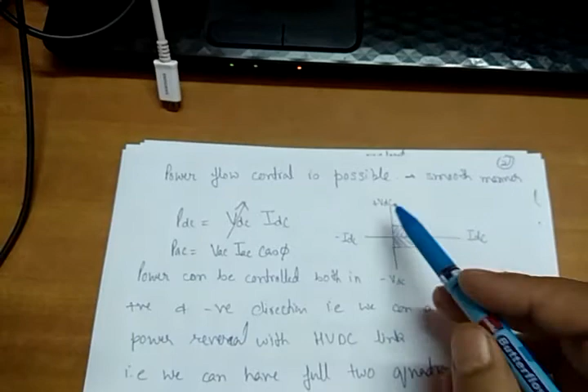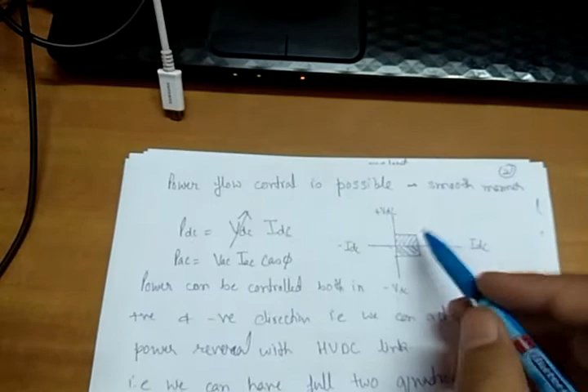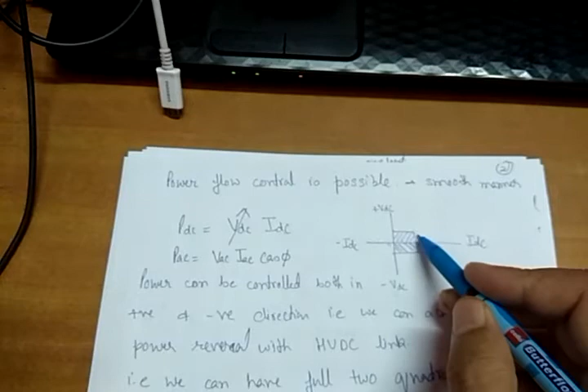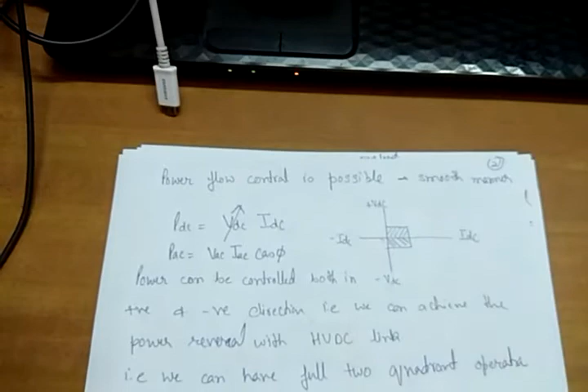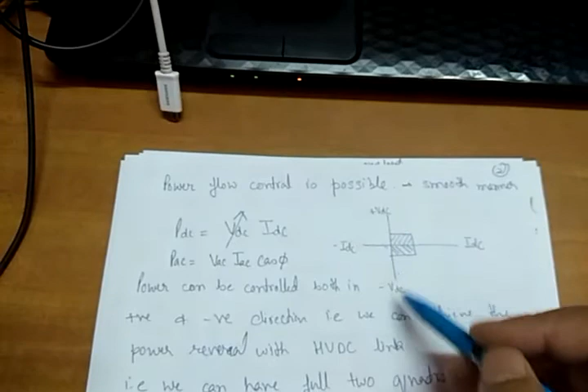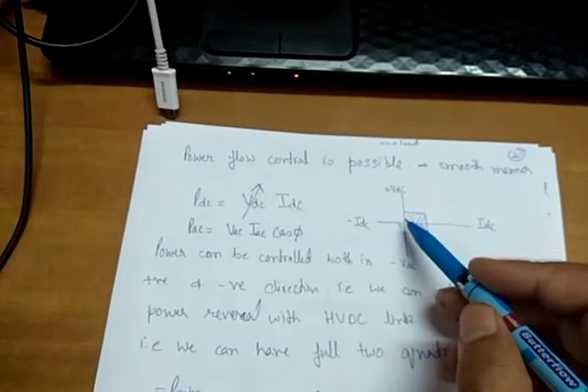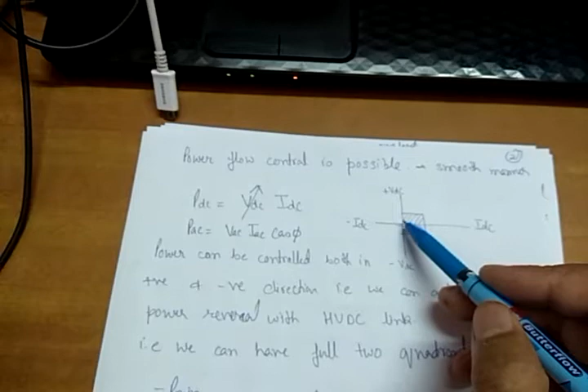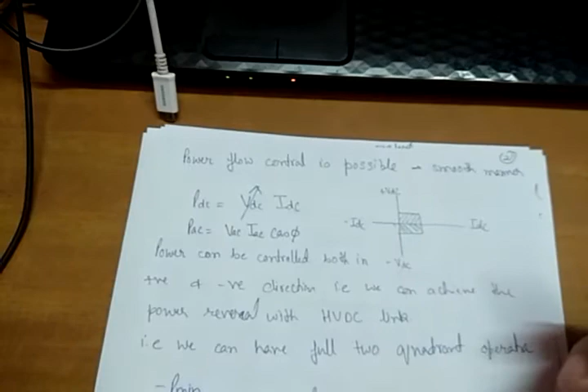This is the current and this is the voltage. Voltage can be varied from 0 to maximum positive and maximum negative value, so it gives us two-quadrant operation of this HVDC system, as shown here. When we make the voltage negative, power will obviously be negative. What do we mean by negative power? Power negative means reversal of power. Power flow can be reversed by controlling the voltage, which is controlled by the firing angle alpha. So power can be controlled both in the positive direction as well as in the negative direction.